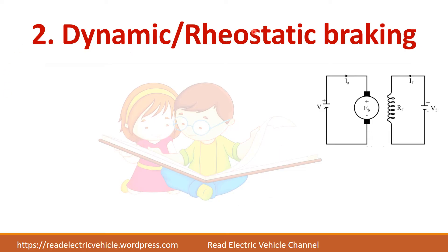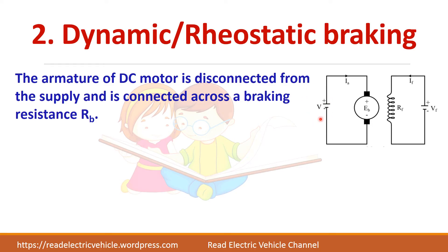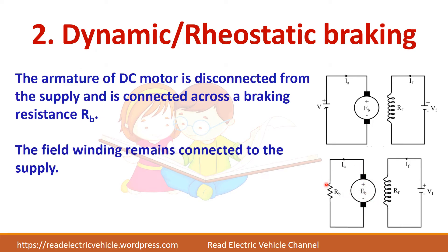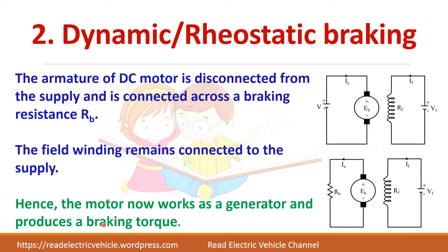Next is dynamic or rheostatic braking. Here the motor is fed from a DC supply with a field winding connected to a DC supply. In dynamic or rheostatic braking, the supply is removed and the motor is connected across a braking resistor — that is why it is called rheostatic braking. Under normal operation, electrical energy is supplied and the machine acts as a motor. Once the supply is removed, the motor acts as a generator and all the energy is wasted in the resistance as heat, producing the braking torque.